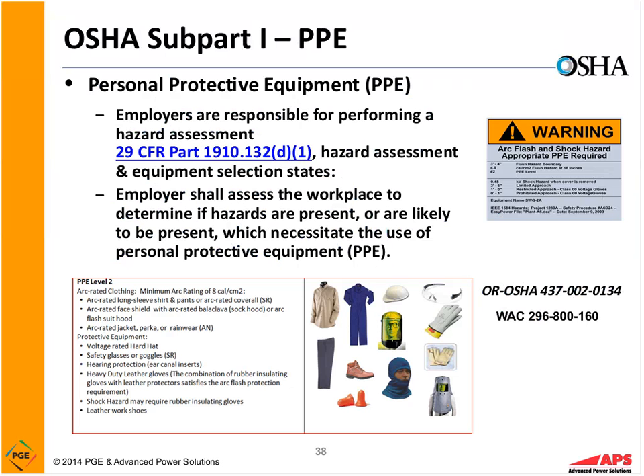So in a nutshell, they're calling for you to assess the hazards and to determine what hazards are present and then what type of PPE will protect folks against hazards. And again, the best approach is to avoid the hazards to begin with. So designing hazards out of systems, whether it be retrofitting equipment or new installations, we want to try and avoid the hazards. But we also need to protect folks with proper personal protective equipment against shock and arc flash hazards and any other hazards that may be present when we're doing electrical work. So again, you can look this information up and get it in full detail on OSHA's website. Again, you're probably going to have to refer to additional information outside of OSHA when you're looking at arc flash hazards such as NFPA 70E.